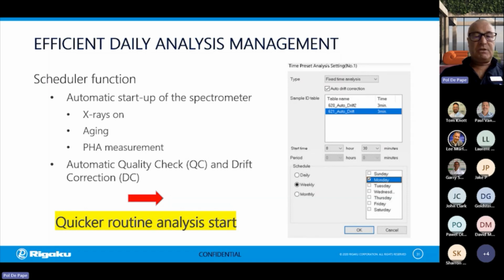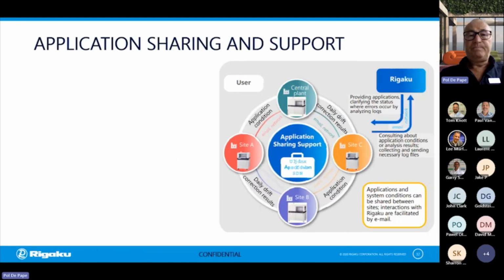Efficient daily analysis management. Very often before you start your analysis, you have to do some preparing analysis, like starting up your spectrometer, doing a PHA measurement, maybe aging your X-ray tube, doing quality check measurements, and drift correction measurements. You can predefine all those measurements on a daily, weekly, or monthly basis, depending on how your routine work is. So before you start working, maybe at 8 in the morning, maybe at 6 in the evening, you can already prepare your spectrometer such that all those analyses have been done. So you can directly start with your routine analysis.